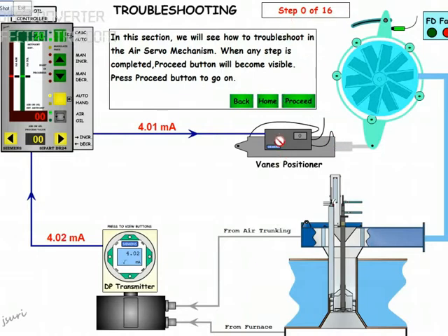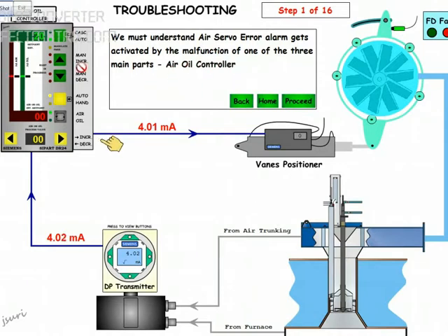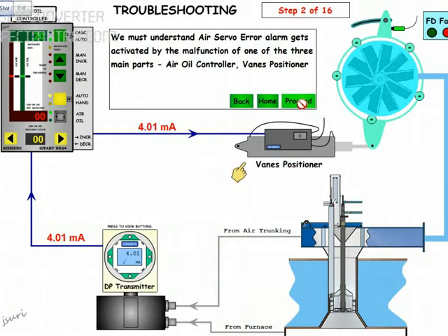Step 1 says we must understand that the air servo error alarm gets activated by the malfunctioning of any of the three main parts: first is the air oil controller, second is the vane positioner, and third is the DP transmitter — the differential pressure transmitter. We are going to identify which one is at fault.